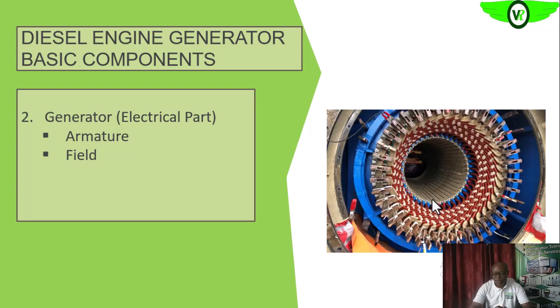In a rotating field generator, the armature is on the stator and we get our power output from the stator. In other instances, the field is on the stator while the armature is on the rotor. That kind of machine is called a stationary field generator, because the part producing the magnetic field needed to induce EMF onto the armature is on the stator, and the armature is on the rotor.